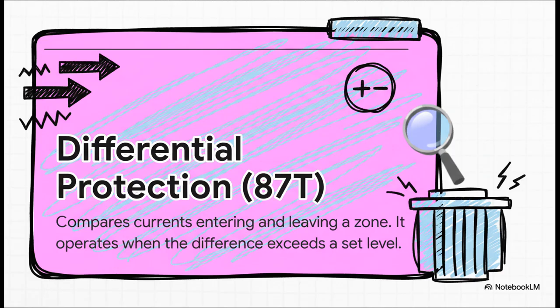The system is constantly measuring the current flowing into the transformer and comparing it to the current flowing out. If those two numbers don't add up perfectly, the system knows. It knows some of that current has gone missing somewhere. It shouldn't. A dead giveaway of an internal fault.